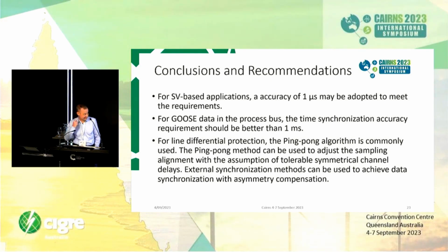For line differential protection, this comes up many times in discussions, because it's important and can be quite tricky. The ping-pong algorithm is used by differential protection devices to calculate the delay between stations. That delay must be used as an offset when they send measurement information, so the data timestamps for the measurement data are adjusted based on the ping-pong results. Someone else probably knows better how it works in practice, but anyway, it can determine the delay between stations, assuming both directions are on the same time reference.